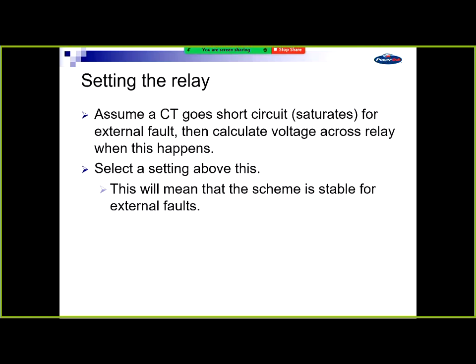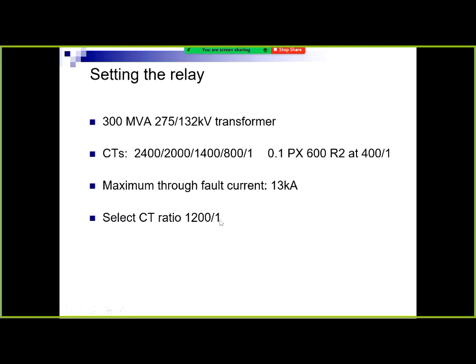The way you set these is you assume one of the CTs saturates for an external fault. You work out the voltage across that CT then, CT's current transformer. You select a setting above this, and that means that the scheme will be stable for external faults. That's how simple they are at setting.